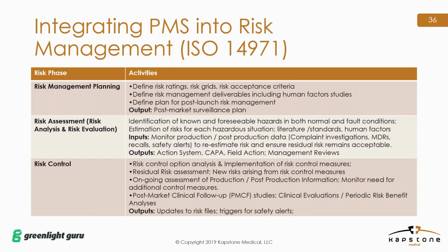So if you are familiar with ISO 14971, which is the risk management standard for medical devices, you have your risk management planning phase. In this phase, you're defining risk ratings and risk acceptance, and you're defining plans for post-launch risk management. One of the outputs of this, as pertaining to post-market surveillance, is the post-market surveillance plan. So you've taken information from pre-market, from your clinical evaluation report, and your post-market surveillance plan is your output.